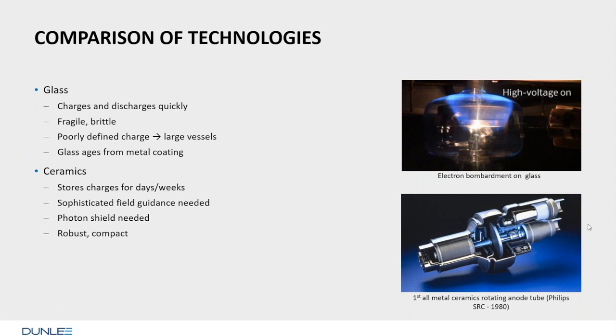Ceramics, on the other hand, is much more compact. And here's the first metal ceramics tube when I joined Philips in 1980. We had trouble with this one because this ceramics was not easy to process. But we put the ceramics far off the focal spot. We shaped the triple points well, and we called it here the field guidance.